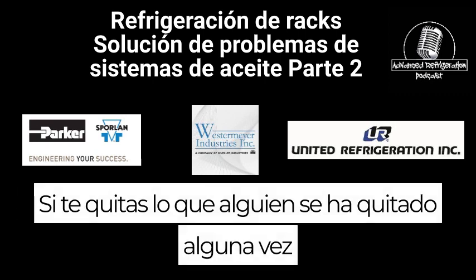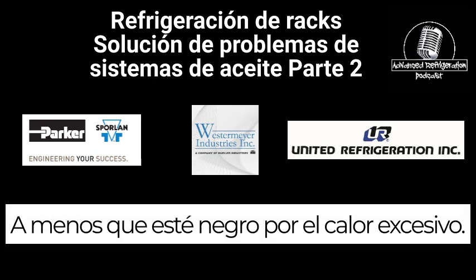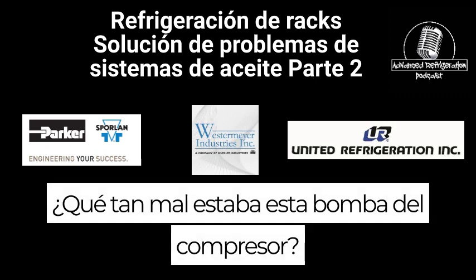If anyone's ever taken off a compressor cover, it's basically the color of steel, right? Unless it's black from excessive heat. This looks like red clay. That's what it looks like. And actually, Kevin, you saw pictures. How bad was this one?